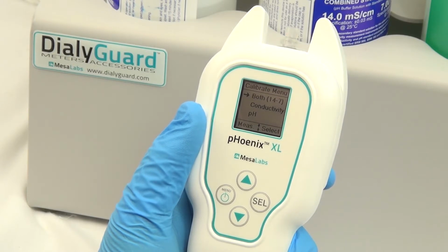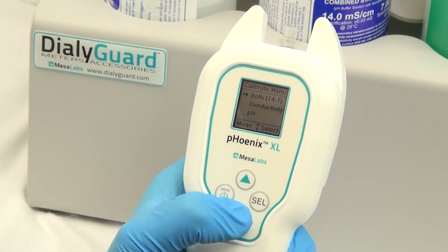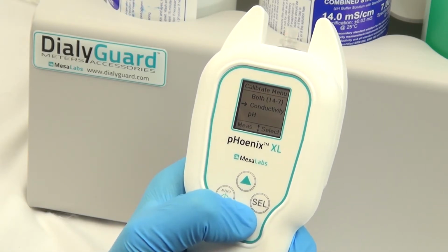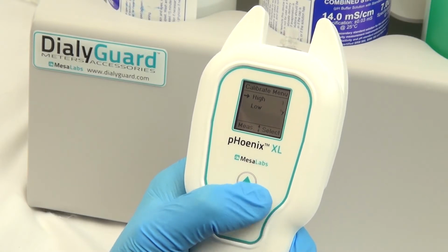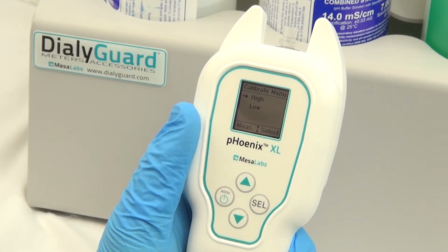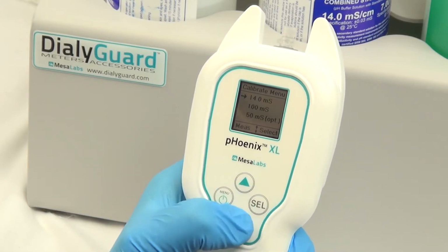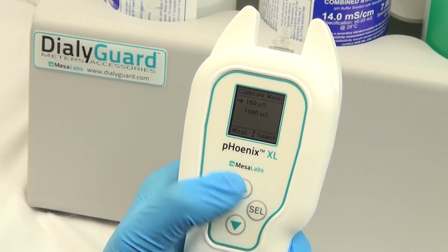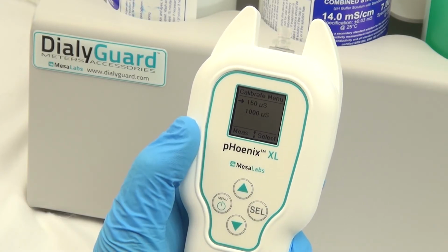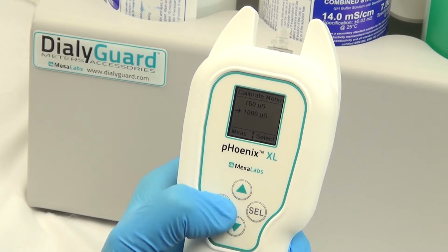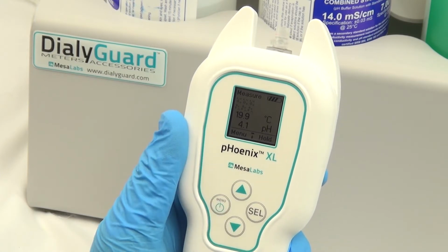If you are using the combination solution, select both. If you are using separate conductivity and pH solutions, select either conductivity or pH. For conductivity calibration, the high selection includes 14 millisiemens, 100 millisiemens, and 50 millisiemens solutions. The low selection includes 150 microsiemens and 1000 microsiemens solutions. For today's demonstration, we will be using conductivity solution.